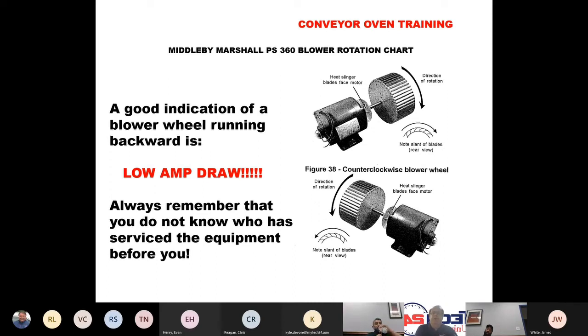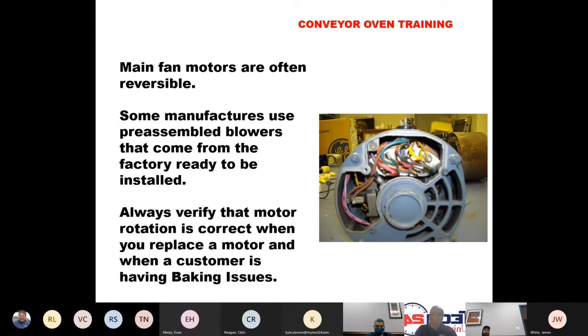If you have two of the same motors in the same oven, your amp draw should be very close, like within 0.2 tenths of an amp. If you've got an amp or two difference, you probably have a direction issue. You should never be more than maybe 0.2 of an amp difference if they're both running in the correct direction. If you have one that's going backwards, it's going to draw significantly lower amps.